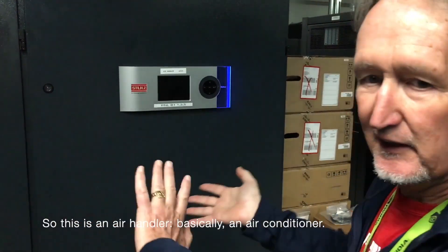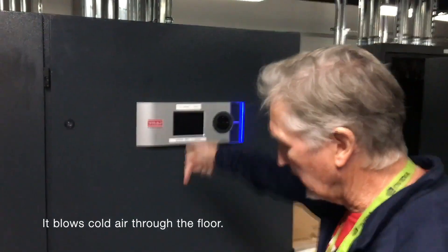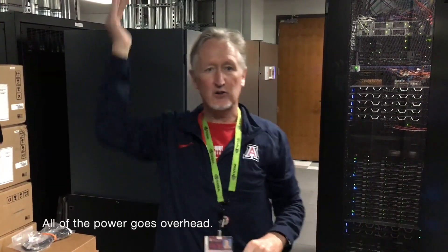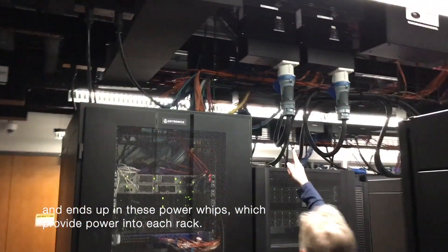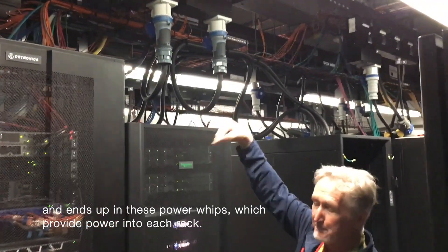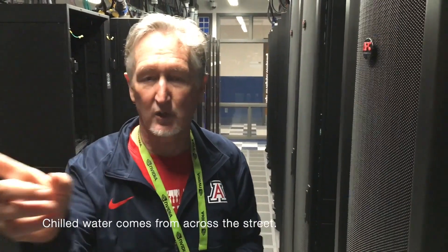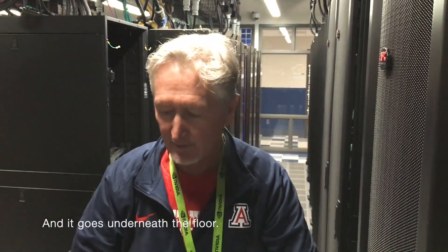This is an air handler — basically an air conditioner. It loads from there to the floor. All of the power goes overhead through steel pipes. The water supply — chilled water — comes from across the street and goes underneath the floor. So all the electricity is overhead with all the power connections, and all the water is under the floor. We keep water and electricity away from each other.